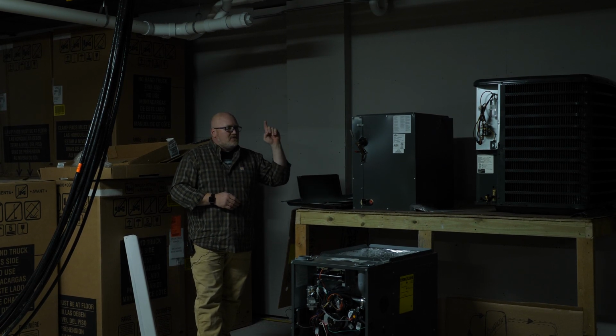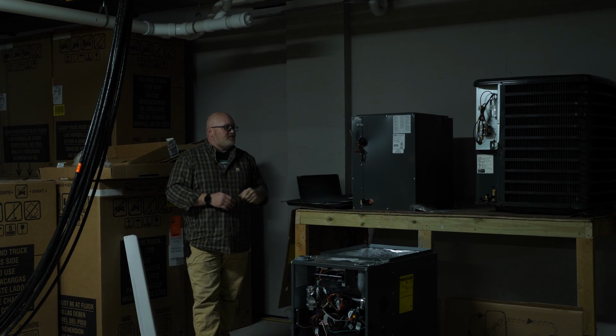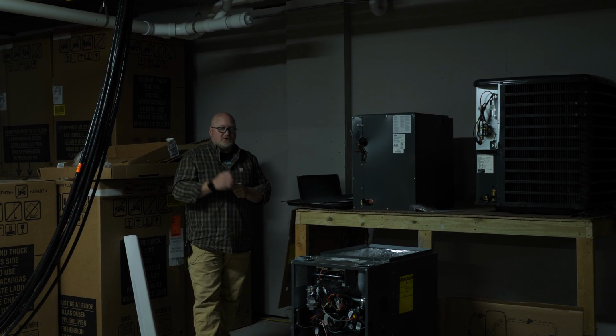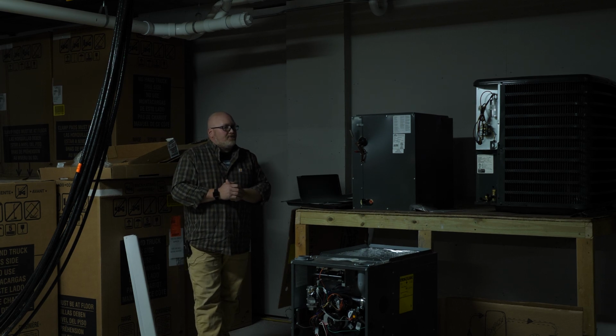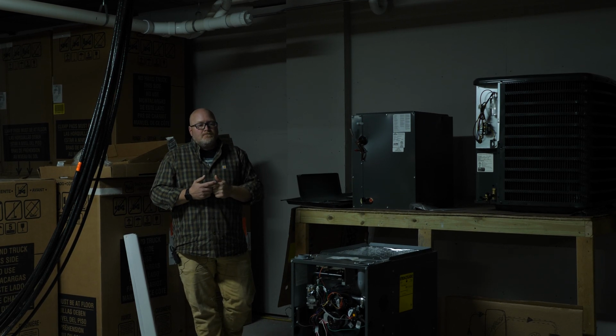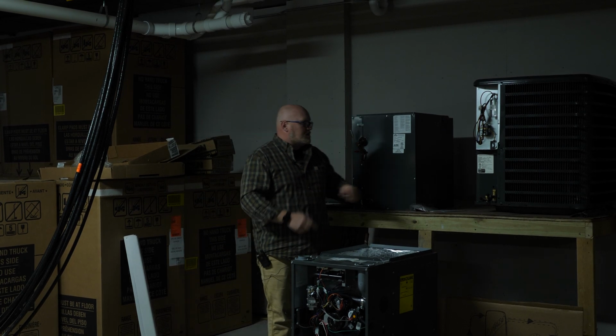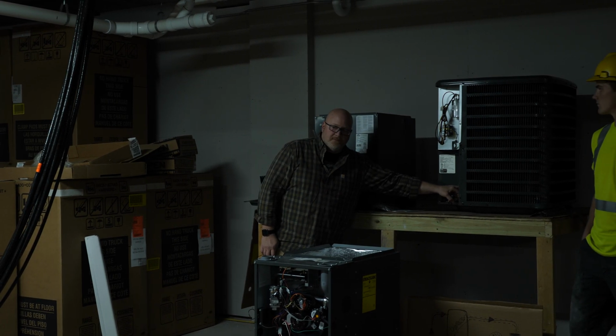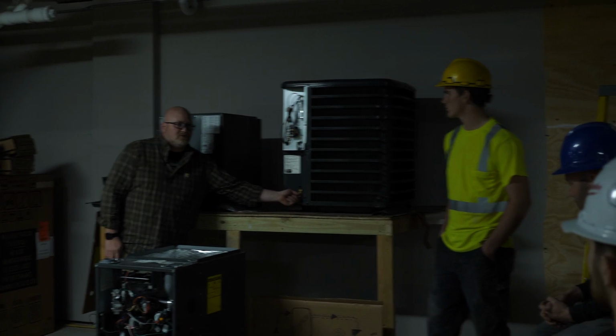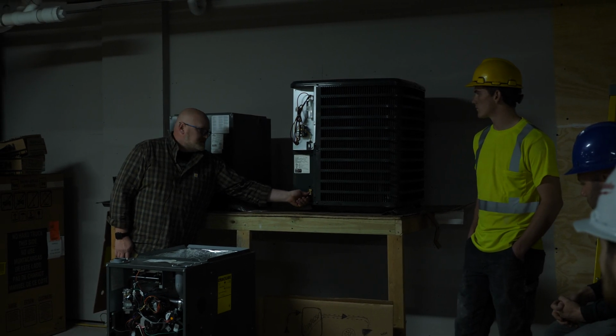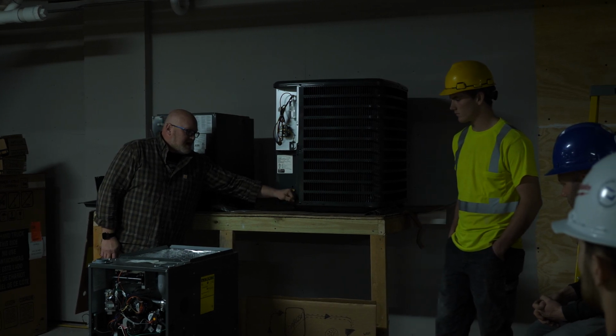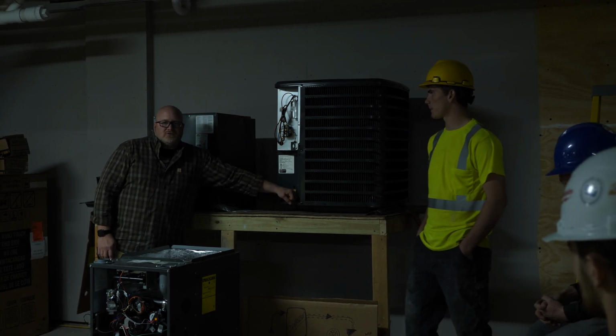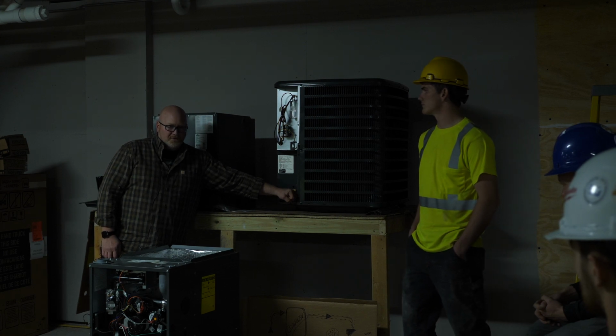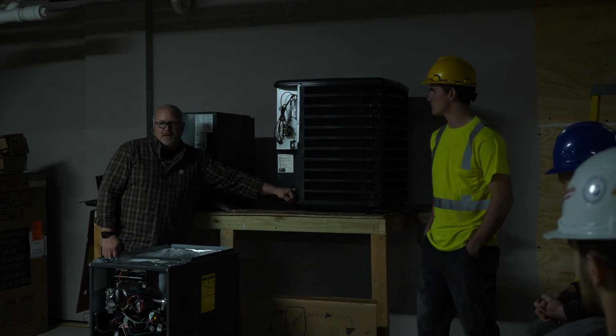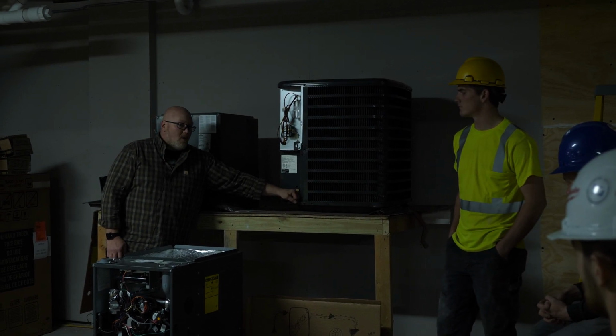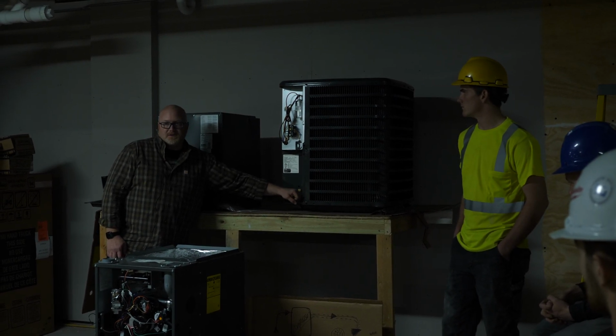Now, let's say you've checked all those things. You've checked your contactor, you've checked your capacitor, your condenser fan motor is running, you've checked your breaker switches and your batteries. Another thing for you to easily identify is if out on your compressor condenser, remember this is your outside unit, you're looking for the larger line, this is the suction line. This is the larger suction line that has a gas in it that should be what industry reference calls beer can cold. If this line is not beer can cold, it is either going to be warm or it's going to have a bunch of frost on it.